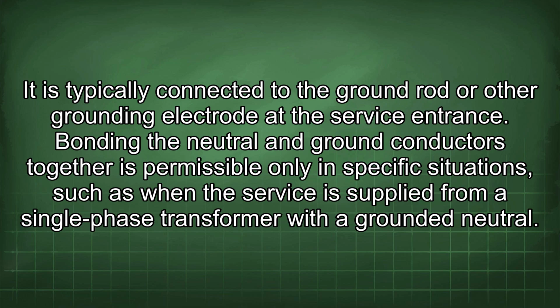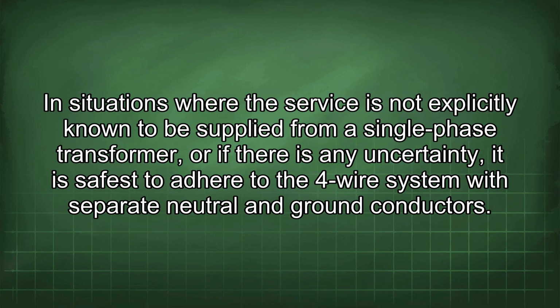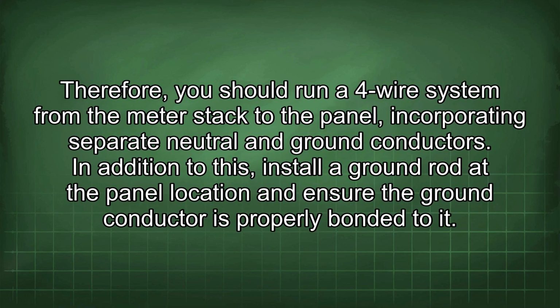Bonding the neutral and ground conductors together is permissible only in specific situations, such as when the service is supplied from a single-phase transformer with the grounded neutral. In situations where the service is not explicitly known to be supplied from a single-phase transformer, or if there is any uncertainty, it is safest to adhere to the 4-wire system with separate neutral and ground conductors. Therefore, you should run a 4-wire system from the meter stack to the panel, incorporating separate neutral and ground conductors.